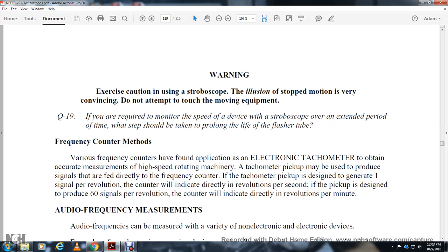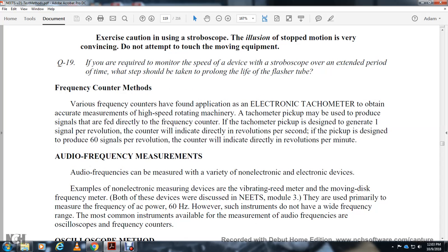Frequency counter method. Various frequency counters have an applicable electronic tachometer to obtain accurate measurement of high-speed rotating machinery. A tachometer pickup may be used to produce the signal directly with the frequency counter. With a pickup designed to generate 1 cycle per revolution, the counter will indicate revolutions per second. With a pickup designed to produce 60 signals per revolution, the counter will indicate the direct revolutions per minute.